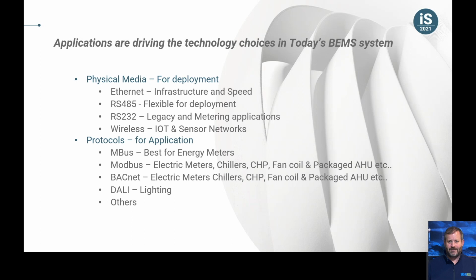Protocols also help define the application, because some protocols suit different devices better. For instance, energy meters are best suited for MBus because they're more battery friendly, and almost all energy meters are now deployed with a battery with a 7 to 10 year battery life. Modbus is the traditional protocol, the first legacy IP protocol that came out. So you saw a lot of energy meters, chillers, CHP, fan coils, and packaged AHUs, all in common. They all have powered devices, so the protocol doesn't have to be as efficient for those items. And then BACnet, of course, is just the latest, and it does almost all the same applications that Modbus does. And then you also have integration to DALI lighting systems, which is another application that requires a different protocol.